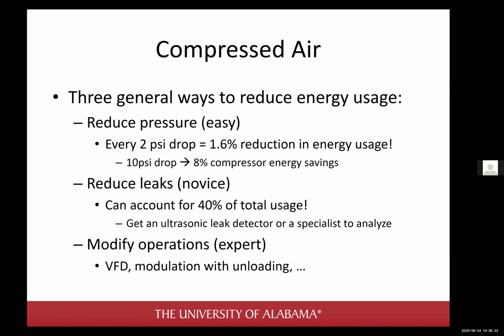Most of the places that I've gone to are floored at how much energy savings can be realized by just turning down the pressure. A rule of thumb that I've written here is every 2 PSI drop gives you a 1.6% reduction in energy usage. So if you can drop by 10 PSI from 110 down to 100 PSI output, you're going to reduce your compressor energy usage by 8%, which really surprised a lot of people. So reducing pressure, super easy to do. Reducing leaks, I've written as the novice way to do it. Yeah, it takes a while to find leaks. It can be difficult to find them.